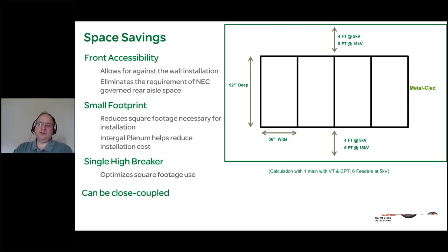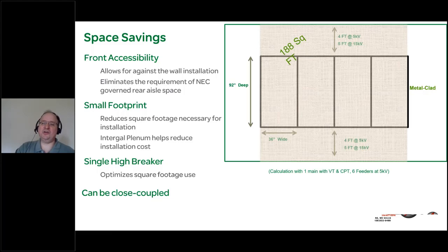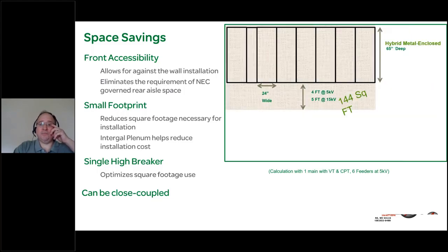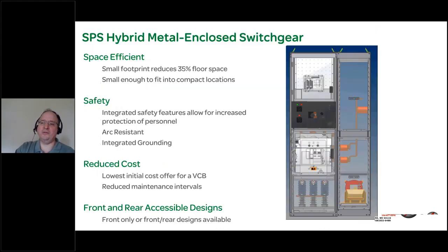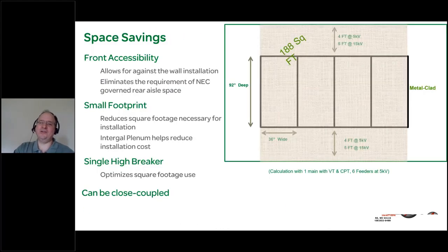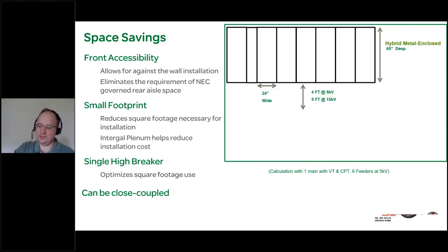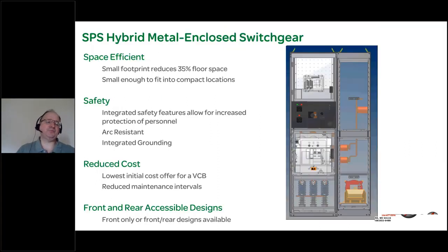This shows a calculation of the space savings with using metal-clad switchgear and the total square footage. This is just something that we sketched up. If we look at the comparable now with the hybrid design I'm showing you, you can see the difference: 144 square feet versus 188 square feet in terms of the space requirement. So, considerable space savings inside the electrical room.